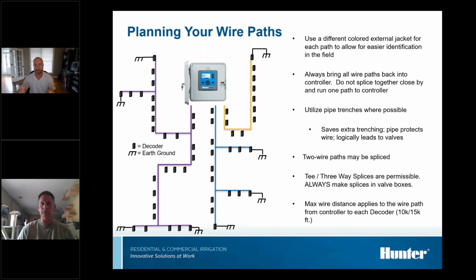Because like I talked about, when you're simplifying troubleshooting, you can remove one wire path out of the clock, remove another wire path out of the clock. If that's in a splice box there, guess what you're going to have to do? You're going to have to break those splices up and then test at that point. So bring all your wire paths all the way back to the clock.